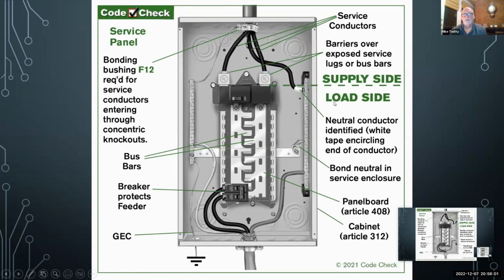Another thing I'm going to point out in here, this neutral conductor is re-identified with white tape. It's a black conductor. It's a bigger wire. That is allowed on number 4 and larger wires. You cannot re-identify a neutral or an equipment ground on smaller wires.